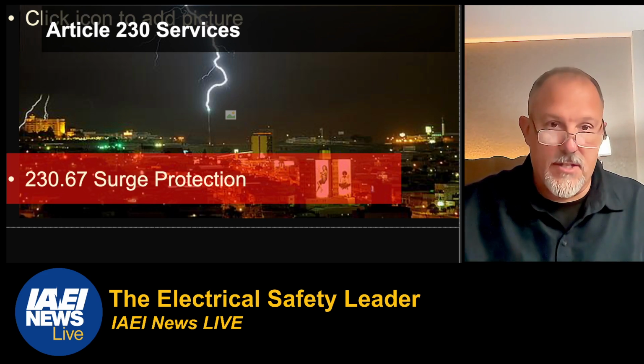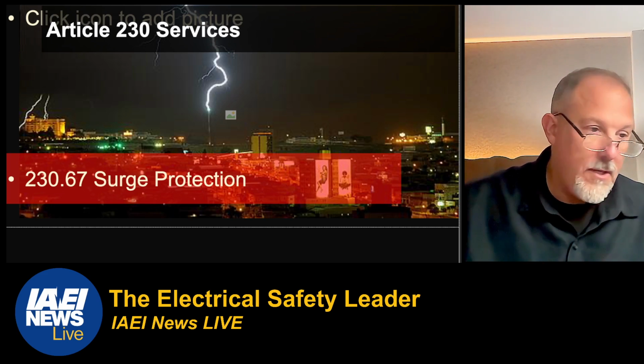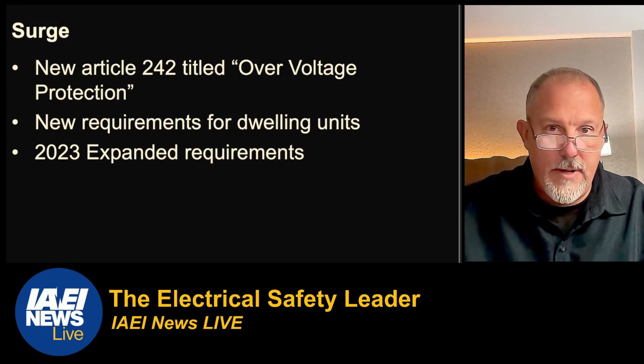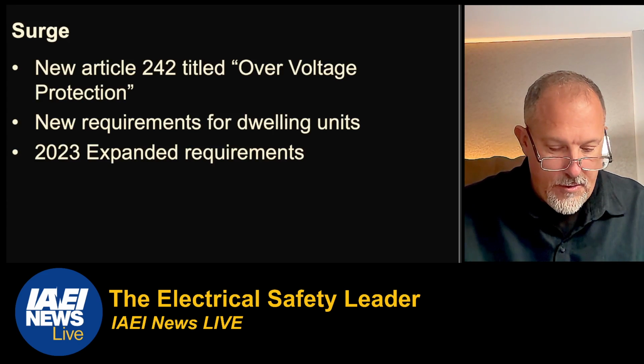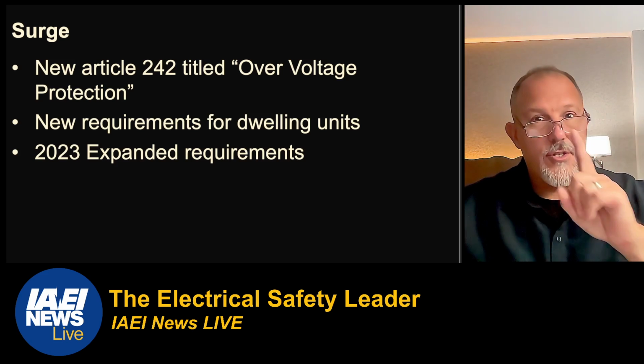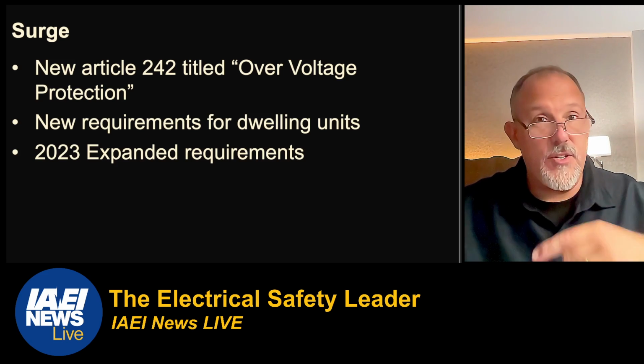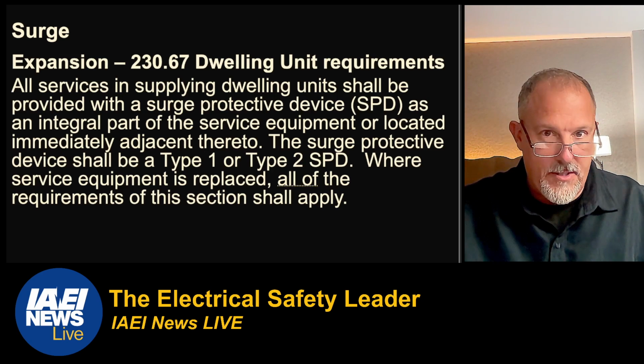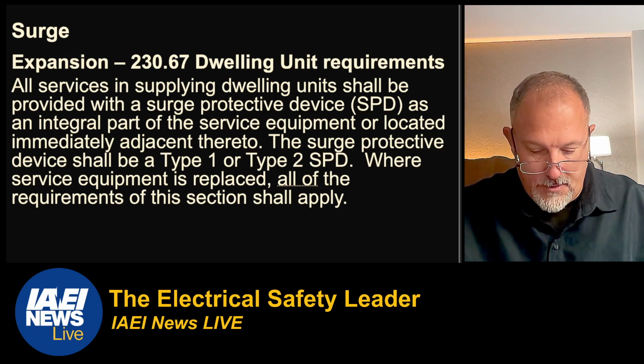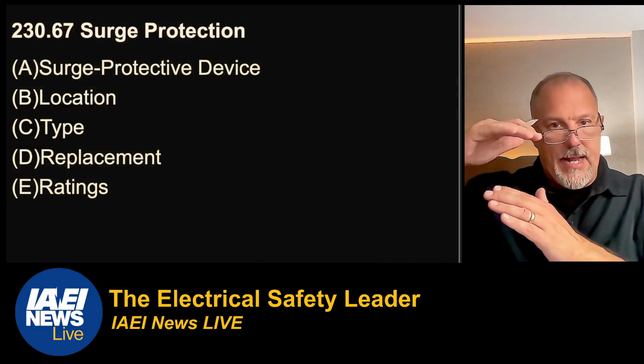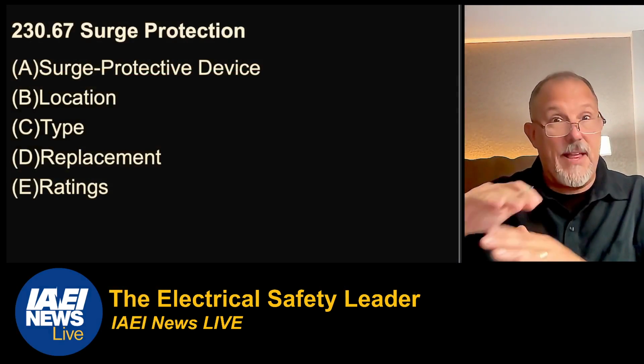Surge is another area that got some love. 230.67. In 2023 we expanded it. Remember, the 2020 code saw the first requirement for surge in dwelling units. 2023 expanded those requirements. So let's go to 230.67, because I'll tell you what they did. All right, so 230.67, we separated A, surge-protective device, B, location, C, type, replacement, and then ratings.